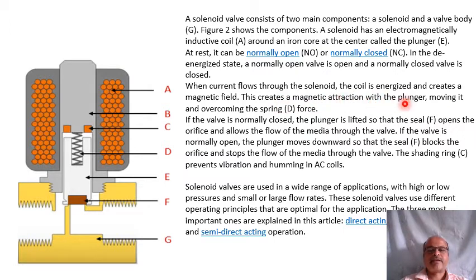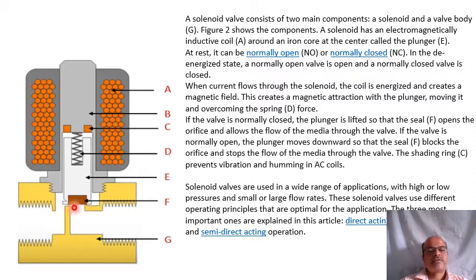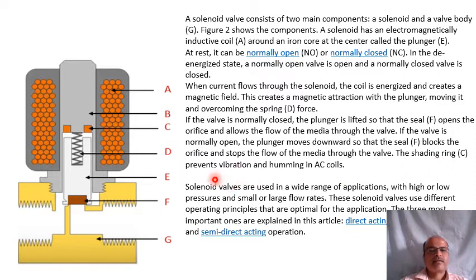If the valve is normally closed, the plunger is lifted so that seal F opens the orifice, allowing the flow of media through the valve. When closed, there is no movement of fluid. If the valve is normally open, the plunger moves downward so that seal F blocks the orifice and stops the flow of media. The shading ring C prevents vibration and humming in AC coils.